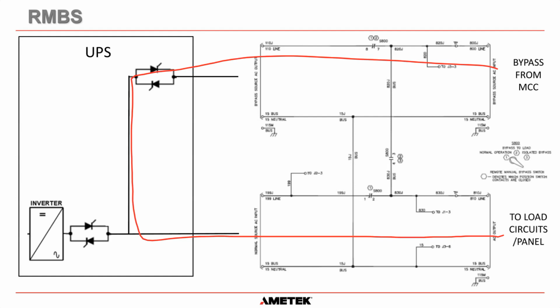And it's important because, remember, that means you are going to have bypass here on this side of the contact, and on this side of the contact, you're going to have bypass as well. So when we move from position 1 to position 2, which is a make before break, this switch here closes, parallels bypass and bypass together, which isn't a problem because they have the same voltage and frequency. And then instantaneously, it will open this contact. Okay?